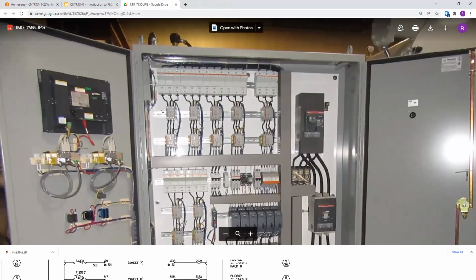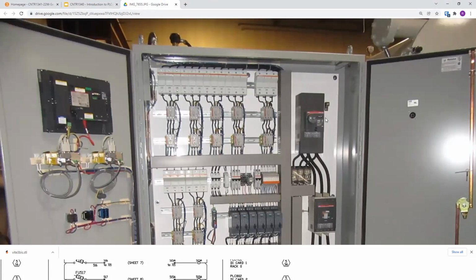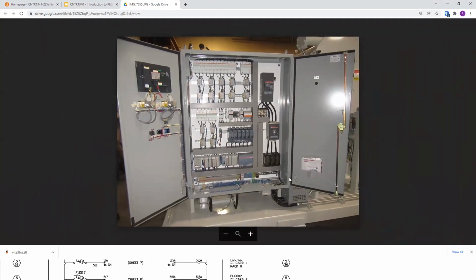That's fine. Again, the top, so the main components of panels. This looks like it is mounted to an external frame, so probably part of a larger assembly. It looks like there's a blower system in back here. So this right here is going to be a main high voltage breaker. What's coming in the top here, 600 volts maybe. So again, this is going to be a higher, more industrial application than strictly PLC.